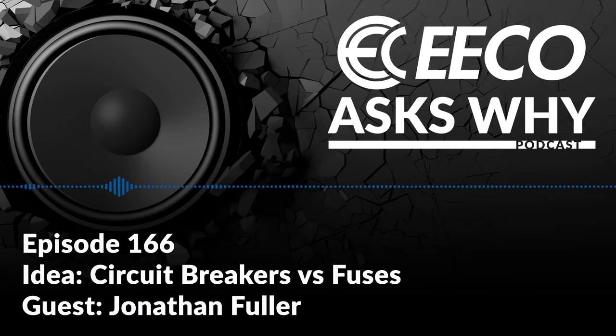So a fuse is going to typically be, if you think of a light bulb in your house, some kind of insulating material with a filament in the middle of it, typically a piece of metal, that when the fuse starts to overheat due to overcurrent, that metal is going to melt or break, and that's going to break your circuit, just like a light bulb in your house. When it burns out, that filament's broken. And then a circuit breaker is more of a mechanical device, and it's going to have a magnetic solenoid inside and sometimes also a bimetallic strip that when it starts to heat up, that strip's going to bend, and that's what's going to actuate your circuit breaker.